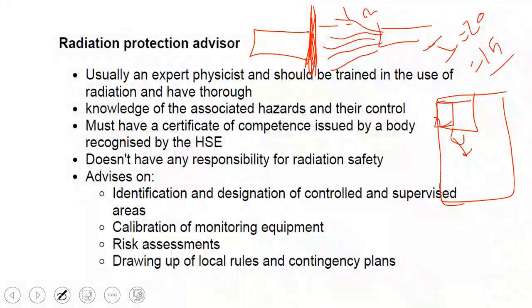Any machine or radiation detector you receive from the manufacturer should have a calibration certificate. This is the word calibration. You are calibrating this thing, right? Well, this calibration means that any machine or radiation detector that comes from your manufacturer should have a calibration certificate, indicating that this device is calibrated with known sources of radioactivity or known strength sources. It should have this energy level or provide you with these values.